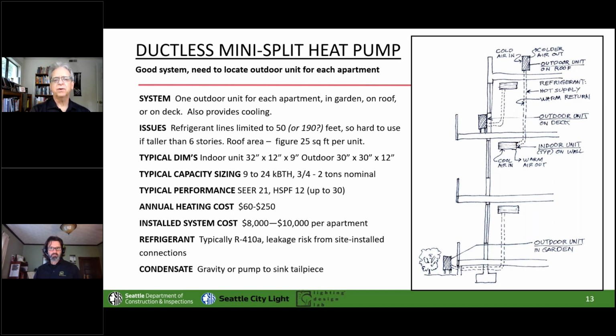That thing under issues where I say refrigerant lines limited to 50 feet. Well, Ben, did I get this right? Was it 190 feet that Mitsubishi is talking about? Yeah, they do have limits of lift, how much up and down you can go before you get oil separation. But yeah, you can go a long way horizontally, and the last one I worked on, it was 40 or 50 feet up, and they were okay. They can also reduce those line lengths and get you a little more lift. So that's a talk to your rep on your equipment sort of thing.